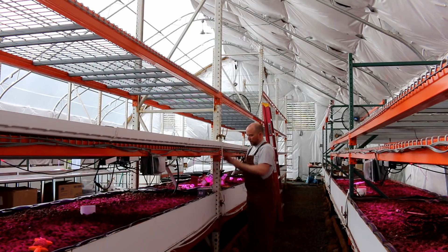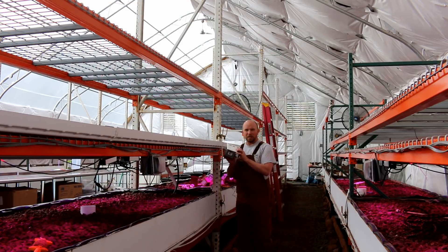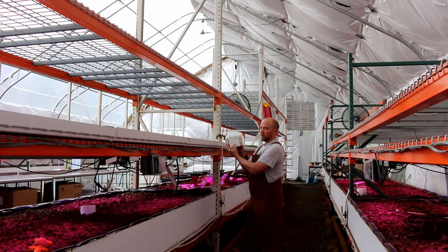We have this valve system set up here going into the existing pump system. The issue is there's just not enough power in the pump to handle this much head plus run valves — it has a 12-foot lift but doesn't have enough pressure when flow is open. I also wanted some backup in case that pump goes down. I programmed fresh code for these units this morning — I'm reusing these, which are what I had on each lane originally when we had the light movers.